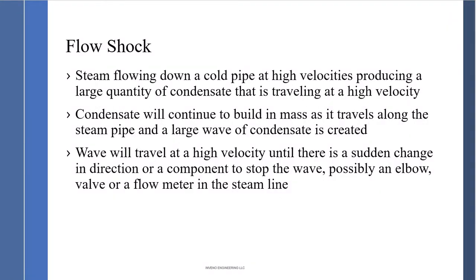The next type of water hammer is flow shock. This occurs when steam blows down a cold pipe at high velocity, producing a large quantity of condensate traveling at high velocity. The condensate builds in mass as it travels, creating a large wave. The wave travels at the same high velocity as the vapor, and a sudden change of direction from an elbow, valve, or flow meter causes a severe flow shock water hammer reaction.